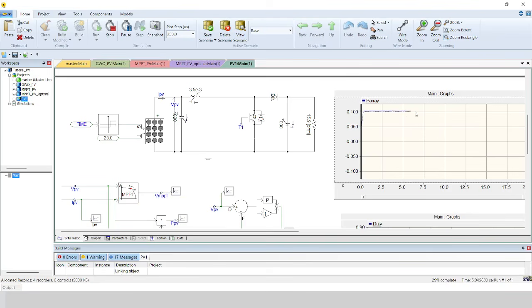So you can see now, for example, this is the output, and you can see the step change. It is not realistic sometimes, unless there is fog or there is shading. As I explained previously, the maximum should be more than 0.05, which is 50 kilowatt.